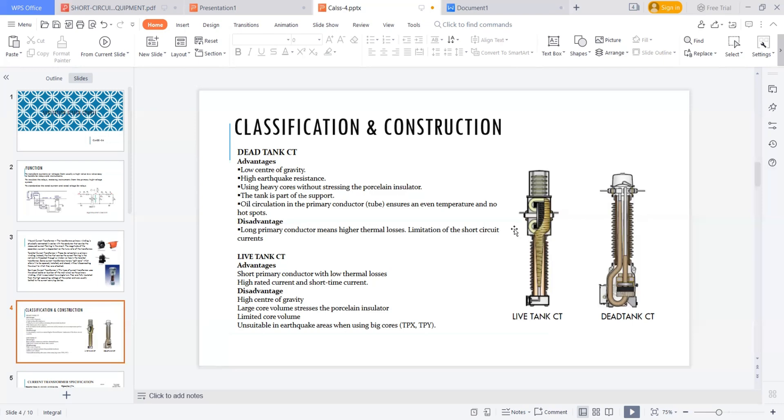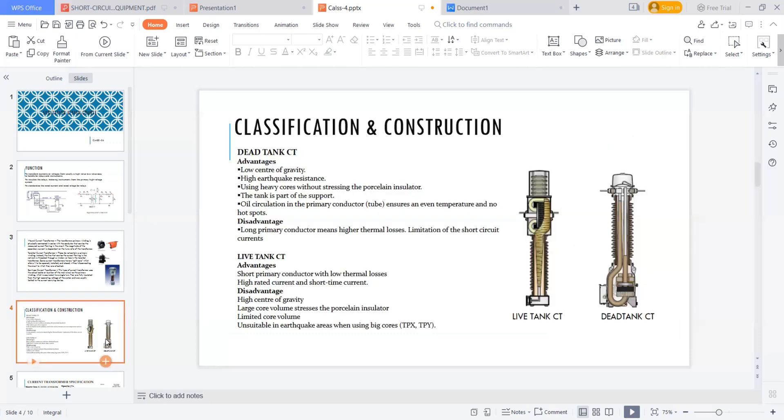If you come to the live tank CT, the primary conductor is very short, only this. So the conductor cost will be low, primary conductor with low thermal losses and high rated current and short time current. What is the disadvantage? So it is placed on this insulator stack having a high center of gravity. So cannot be withstand for earthquake zone areas, which zones are particularly prone to earthquakes, and large core volume stresses. This tank is on the top of the insulator stack. So obviously this insulator stack will get stresses by this tank placed on it. So this is the disadvantage of live tanks.